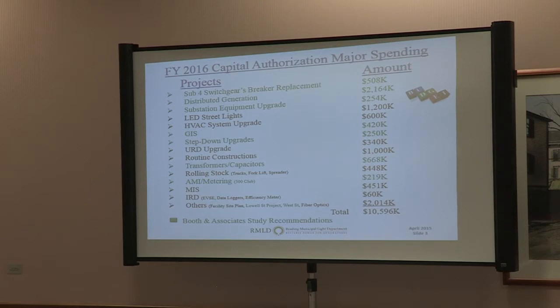We're actually getting the most bang for our buck because the system is capable of doing two things. One is reading the meters we currently can't get information out of - there are 60 of them. The second thing is distribution automation, which lets us bring field device information, the IEDs, back from the field to the SCADA and OMS system for analysis and for activating FDIR - fault detection, isolation, restoration - which means improving overall reliability. This system is capable of handling both.